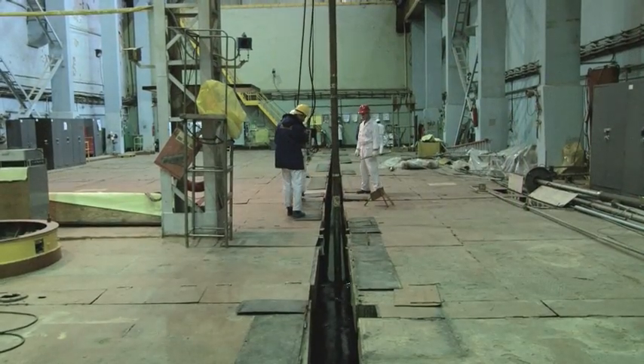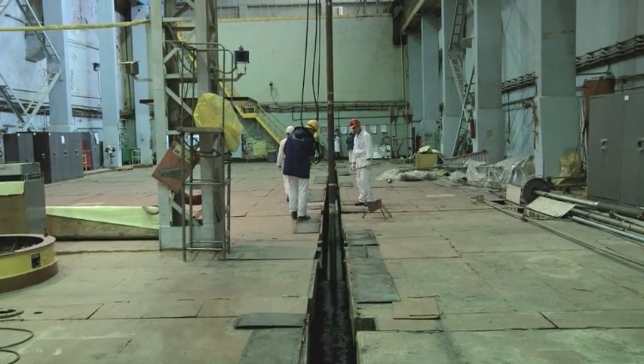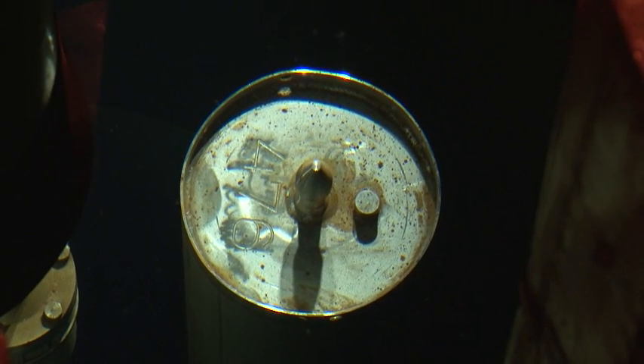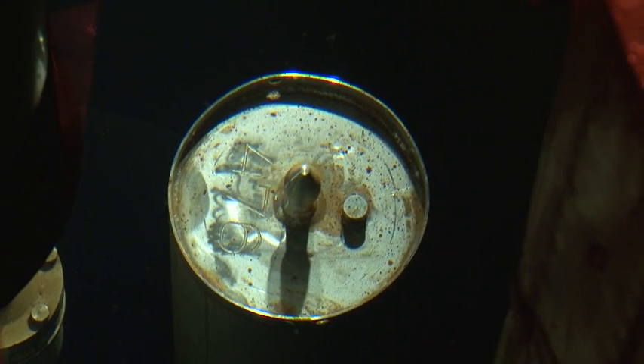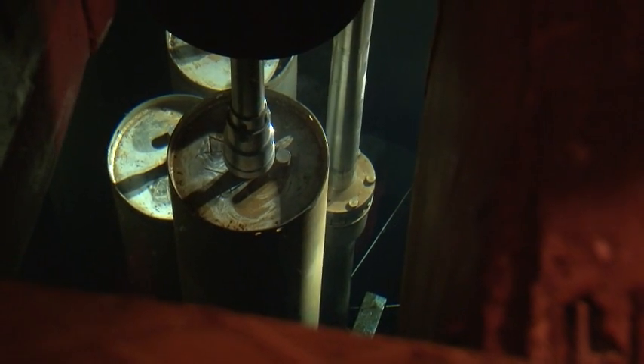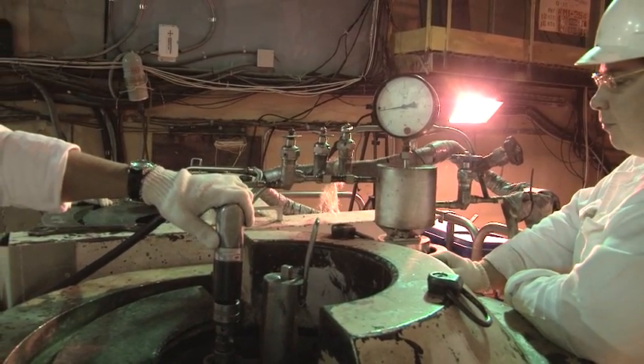Once the spent nuclear fuel elements had been sealed in storage canisters, the canisters were then placed into baskets in the spent fuel pool. This underwater storage provided biological shielding as well as thermal cooling. Some of the canisters had remained underwater for more than 10 years. As a result, it was required that a check for leak tightness be conducted.